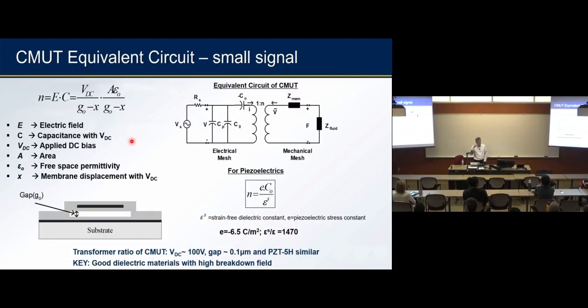If you look at it as an electromechanical device, you would look at this basic electromechanical equivalent circuit, and this turns ratio is important because it tells you how much force you get for a given voltage that you input to the device. For a piezoelectric device, it's given by these material constants. If you look at PZT5H, a standard piezo material, these are the numbers. But to get to those kinds of transformer ratios for a CMUT, you need to apply like 100 volts over maybe a 100 nanometer or 1 micron gap. So it's not an easy task. You have to put lots of electric field on that material.